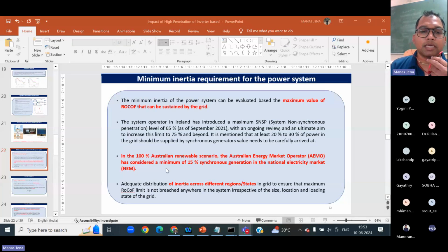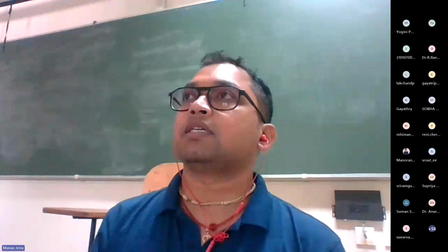So you can see that in the Australian grid, they have decided that a minimum of 15% synchronous generation should be there. As far as the Ireland grid is concerned, their target in 2021 was 65%. They have come up with a quantity called SNSP, system non-synchronous penetration. With 65% they have an ongoing review, and their ultimate aim is to increase the limit to 75% and beyond. But it is mentioned that at least 20 to 30% of the power in the grid should be supplied by synchronous generators. So essentially both of them are on the same page. Perhaps once we reach 50%, we should see how to go about it. RoCoF is one of the criteria. I hope I could address this.